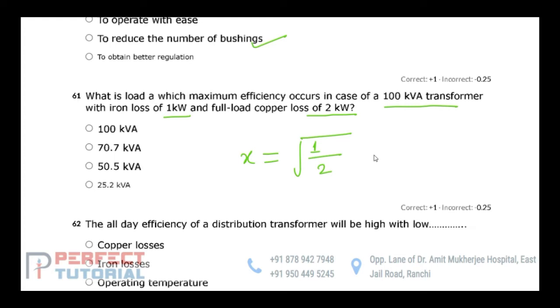Now, simply, it is asking what the load kVA will be. The load kVA at which maximum efficiency occurs is equal to the fraction of loading at which maximum efficiency occurs multiplied by the full load kVA. So the load kVA at which maximum efficiency occurs would be 100 multiplied by 1 by root 2, that is the fraction of loading at which maximum efficiency occurs. It will give 70.7 kVA.